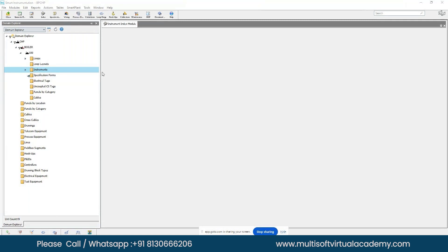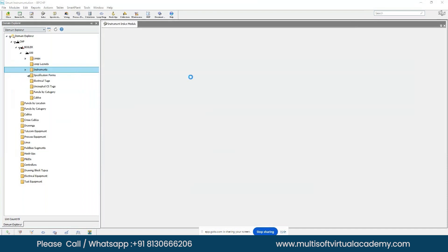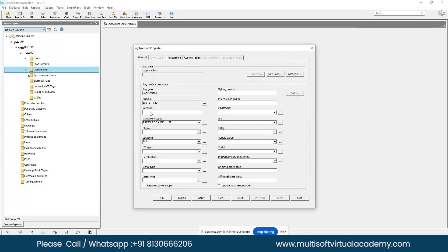To create a new tag number, right-click on the Instruments folder and select 'New Instrument'. You will get the same pop-up window as in the Index Module. Fill in all the necessary information. You can create any type of instrument here, including those not available by default, such as a vibration transmitter.